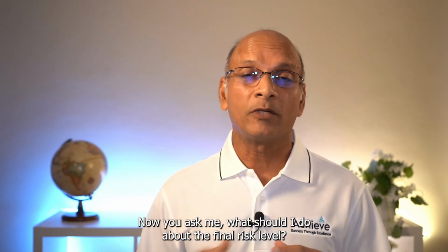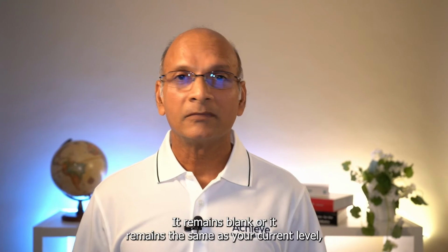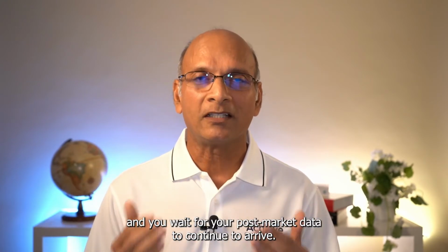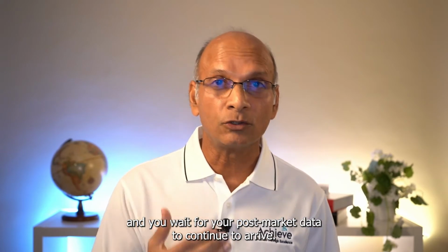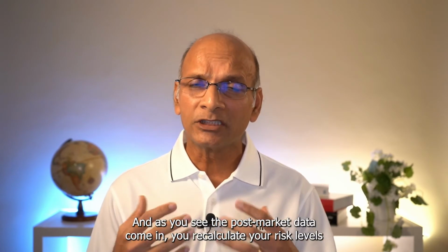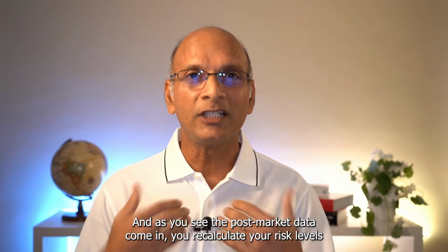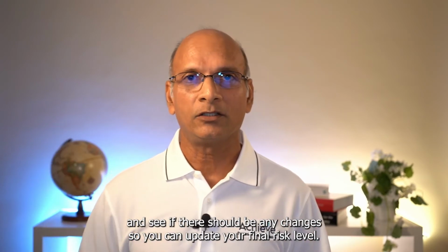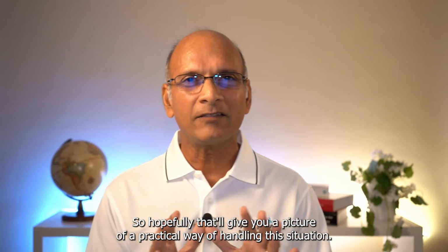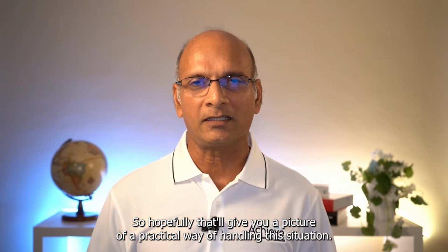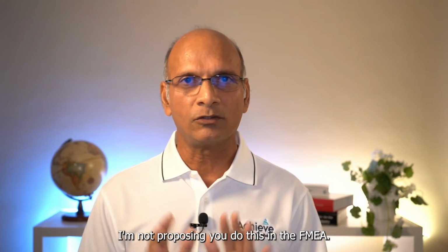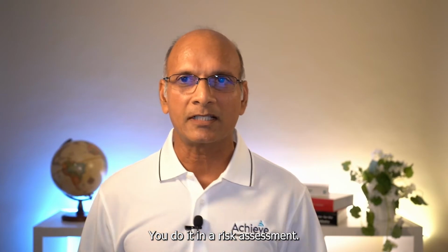Now you ask me, what should I do about the final risk level? It remains blank, or it remains the same as your current level. And you wait for your post-market data to continue to arrive. And as you see the post-market data come in, you recalculate your risk levels and see if there should be any changes, so you can update your final risk level. So hopefully that will give you a picture of a practical way of handling this situation. We're not going to do this in the FMEA, by the way. I'm not proposing you do this in an FMEA. You do it in a risk assessment.